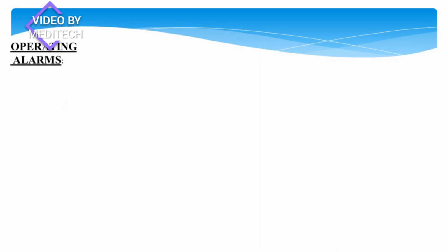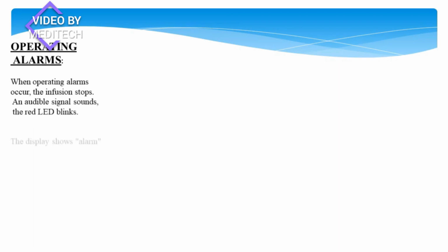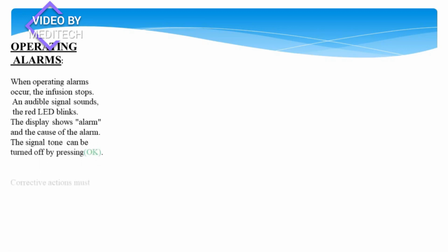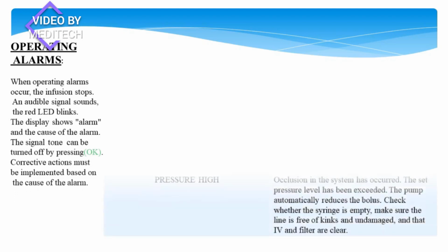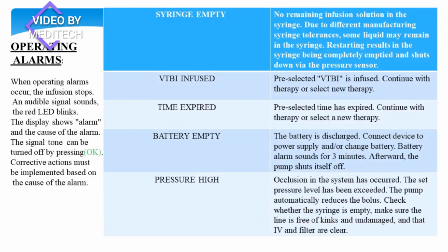Operating alarms. When an operating alarm occurs, the infusion stops. An audible signal sounds and the red LED blinks. The display shows alarm and the cause of the alarm. The signal tone can be turned off by pressing the OK button. Corrective actions must be implemented based on the cause of the alarm. Let's see the cause of some alarms.